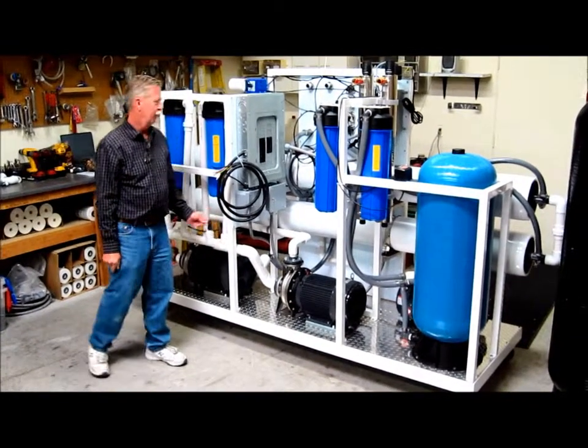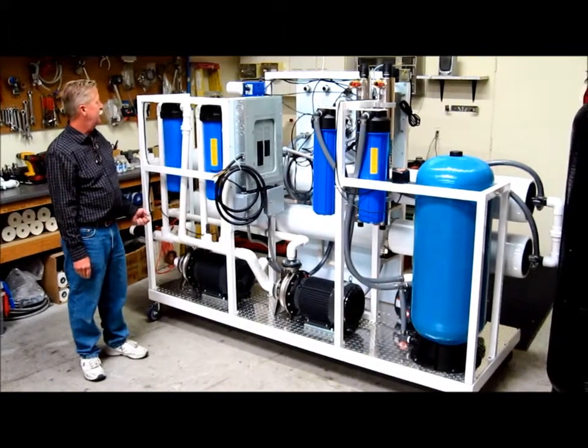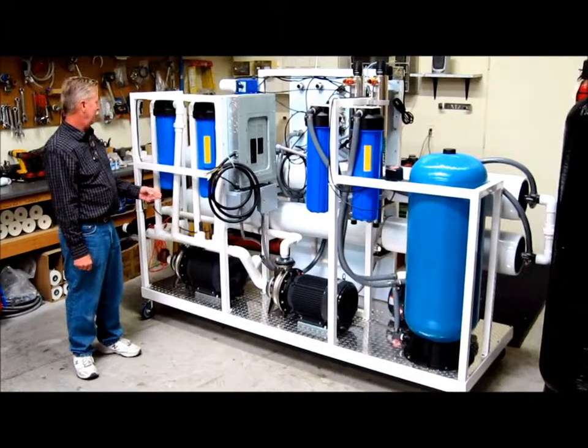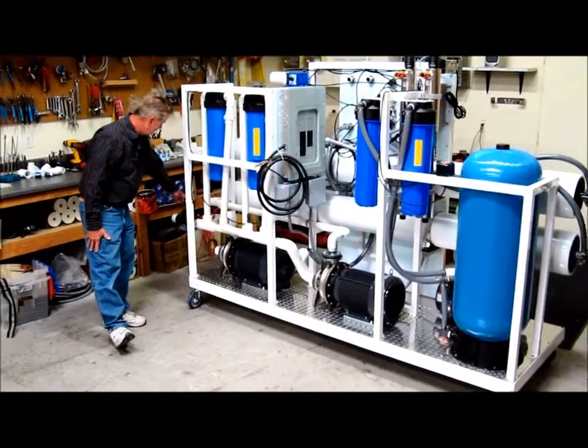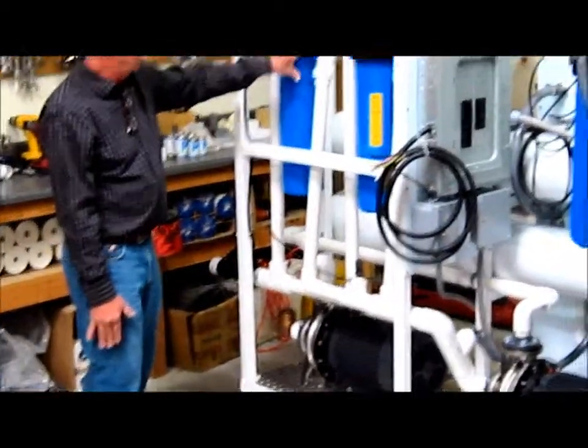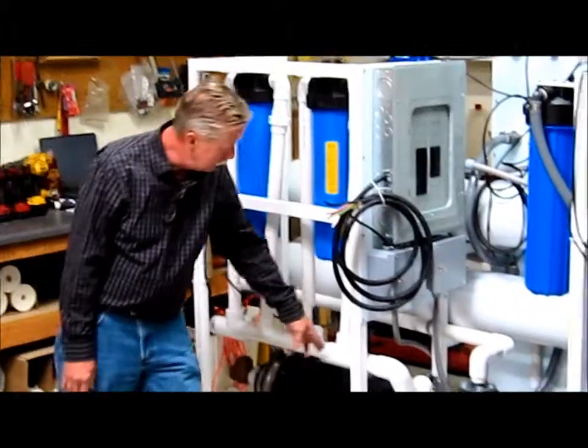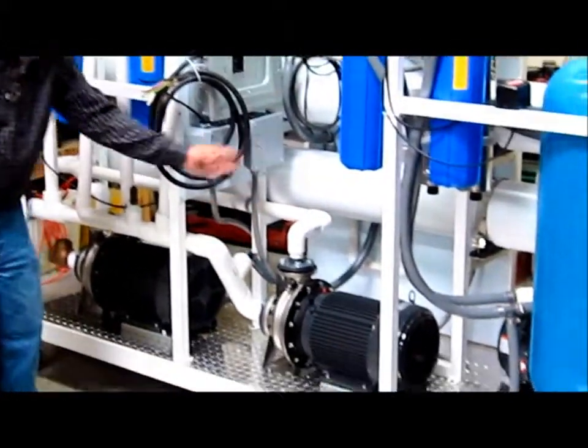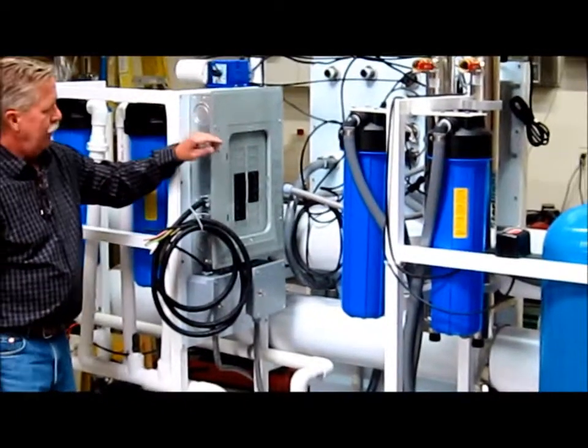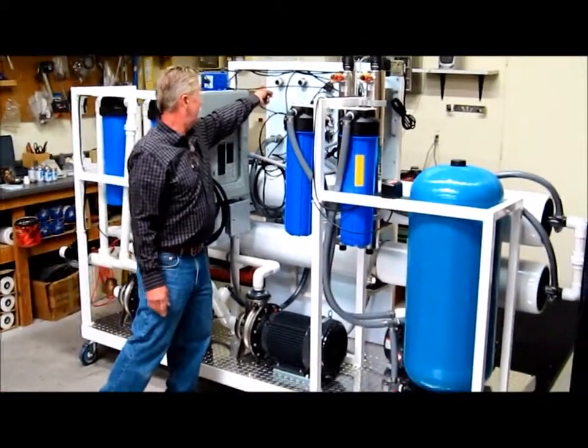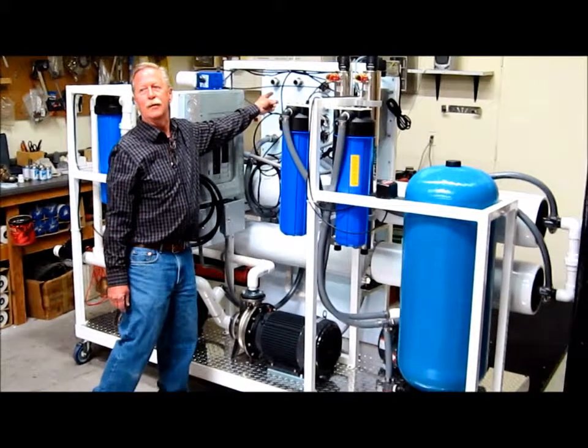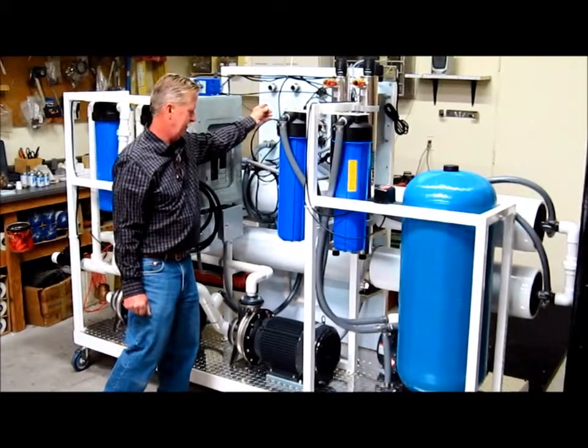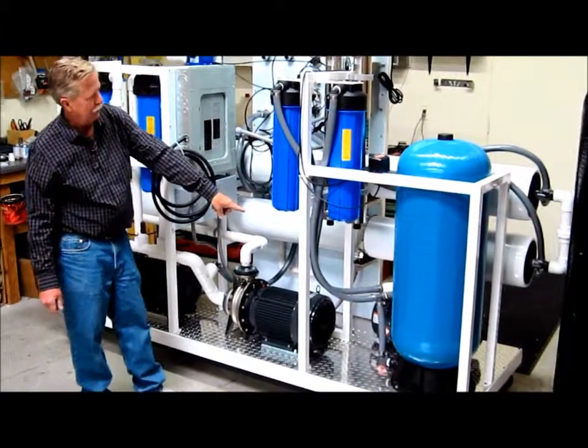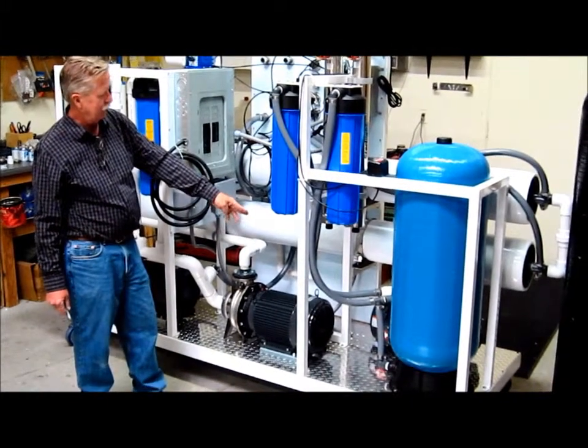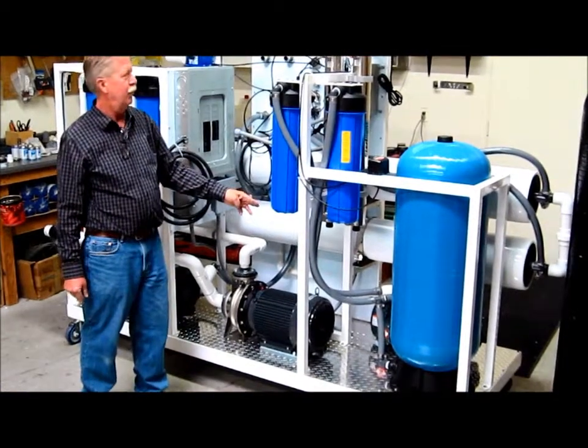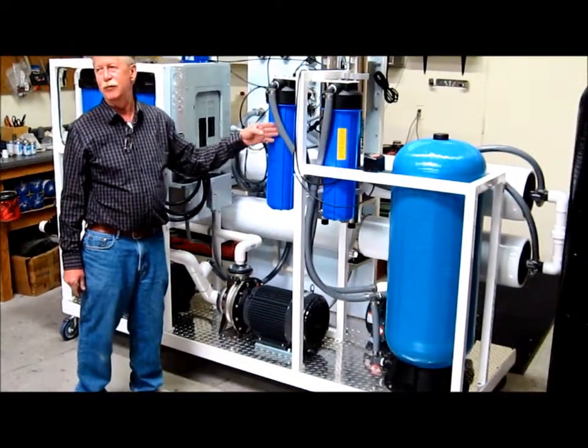Here we have the back of the reverse osmosis system. A lot of people won't really show you a whole lot about what's going on these. Again, we have where the water comes into the system, flows up through the dual pre-filters, into the RO pump, then out to the membranes. Once it goes through the membranes, you've got connections up here and here for the water that would go into the tank and for the wastewater. Again, we showed you the pump over there where the connection is on that, so you really don't need to see it from there. But that's the pump that delivers the water to whatever type of use you're using, the filler or whatever.